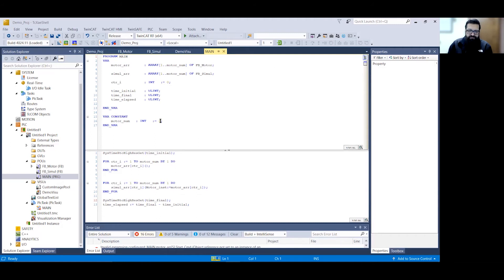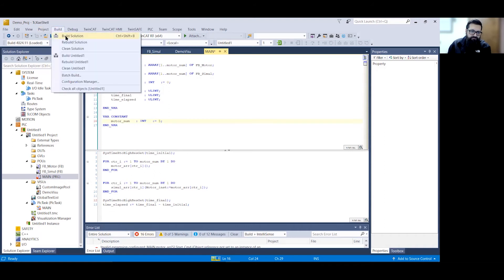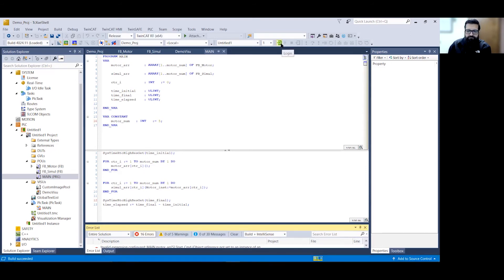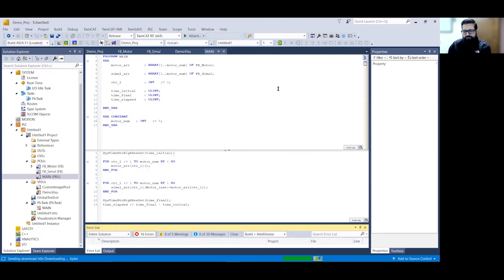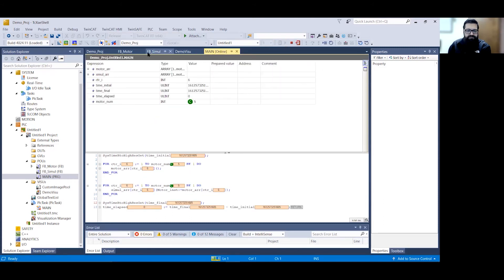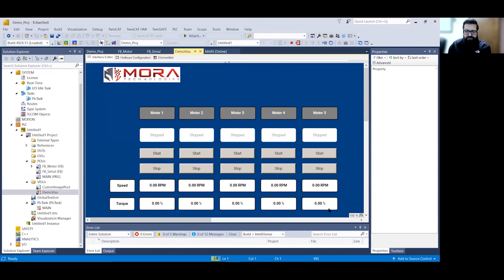This is why the visualization only allows working with three start/stop controls and speed/torque feedback — I've only specified three instances of the function block motor type. But if I change this constant to five and rebuild the project, then log in with download and start the PLC, you can see those errors have cleared. I can now start and stop motor four and five, and they operate with the same behavior as motors one through three, because they're all patterned off the same function block.